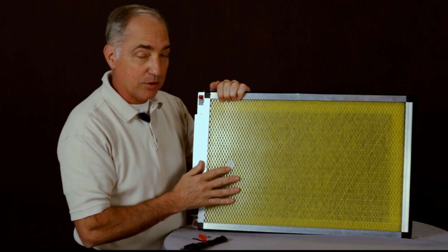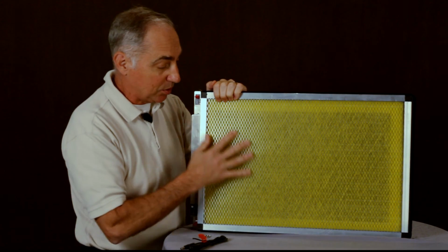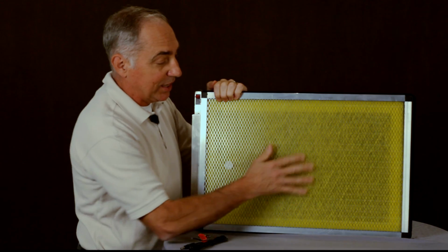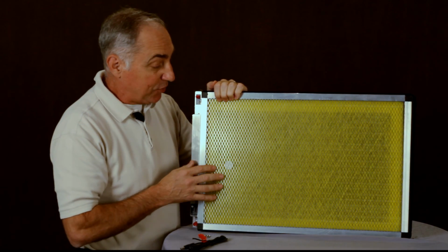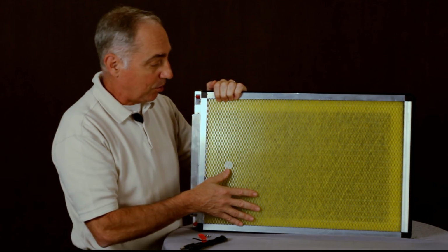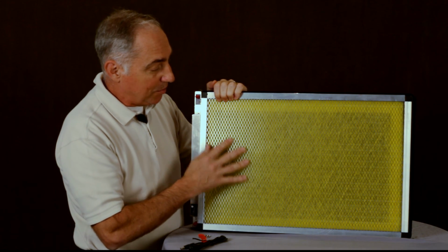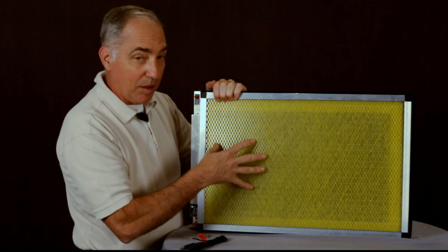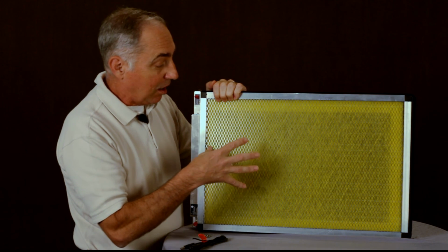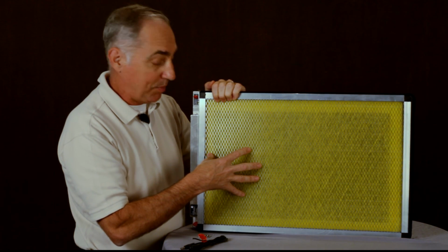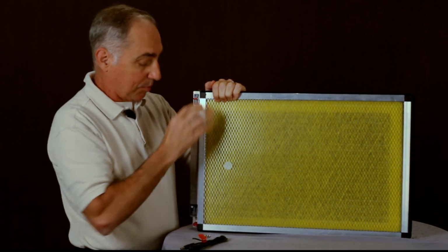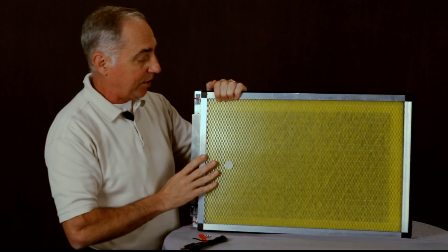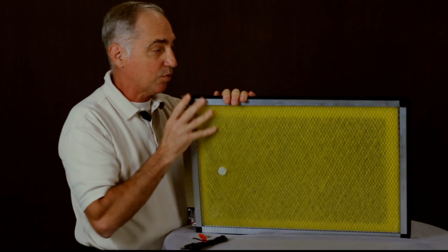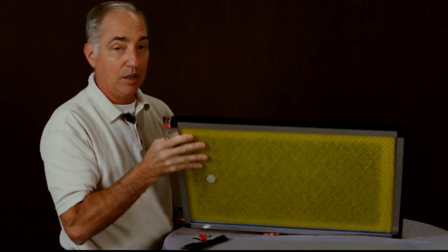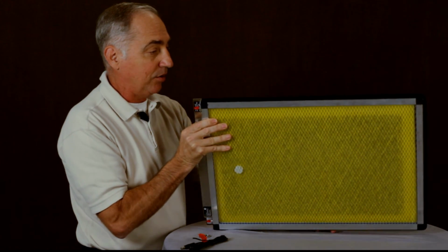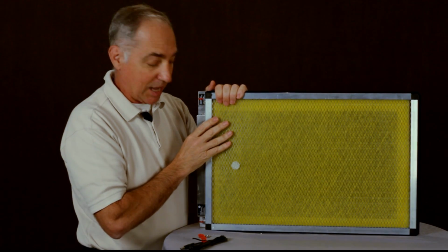Occasionally, with a wider mesh screen, we don't have this problem like we used to, but with the narrower screen, we used to get a lot of gauzing on here. You could vacuum that off. If you still have that, you can vacuum these and keep the pressure drop low. But occasionally, you may have to do that as it builds up in here. But you're still going to get the 3 to 4 months of electroplating of particles onto the pad in and of itself. So here again, just a couple of little reminders, different clips in a different area. The brush seal helps with blow-by as well. As you can see, we've got a brush seal all around the whole thing, which makes it easier to slide in and out. And it also gives us a better seal to stop the blow-by.